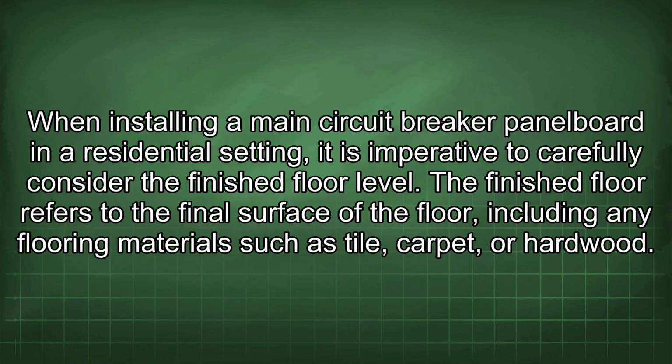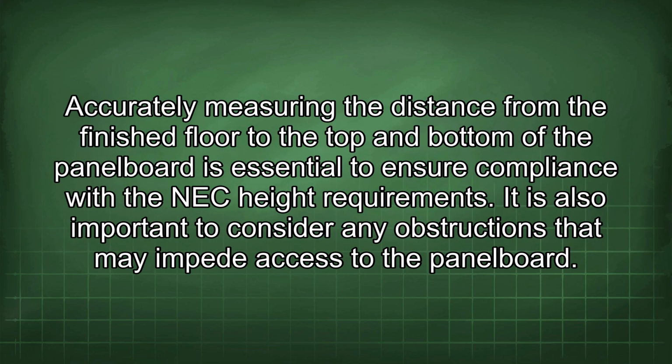When installing a main circuit breaker panel board in a residential setting, it is imperative to carefully consider the finished floor level. The finished floor refers to the final surface of the floor, including any flooring materials such as tile, carpet, or hardwood. Accurately measuring the distance from the finished floor to the top and bottom of the panel board is essential to ensure compliance with the NEC height requirements.